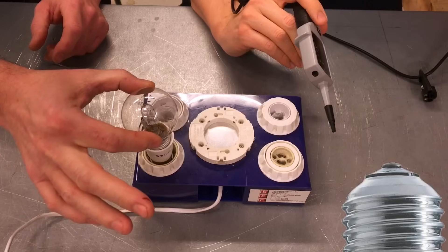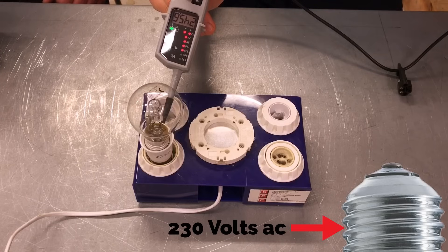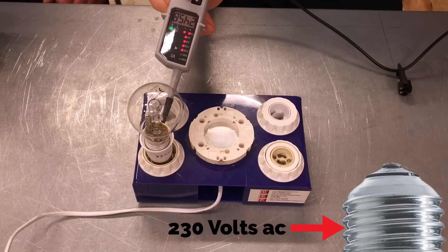Genuinely, we've not set that up. It's live. So we've just accidentally connected that up the wrong way round. So let's just drop that on as a customer might have done. How much of that cap is now exposed? If your hand slips down, all of a sudden you're contacting a live part. That is not safe. Incredibly unsafe.